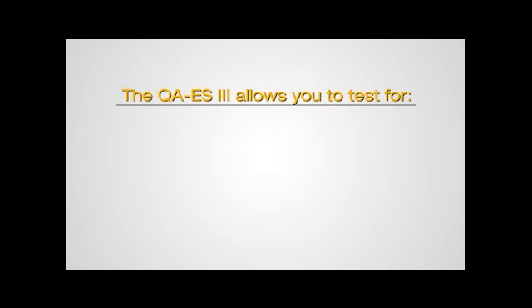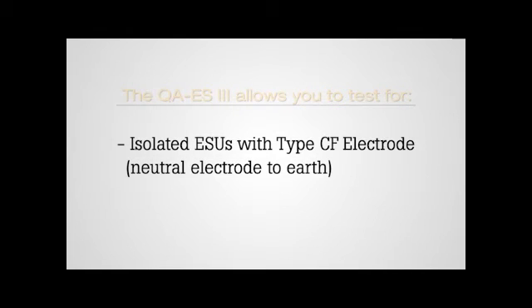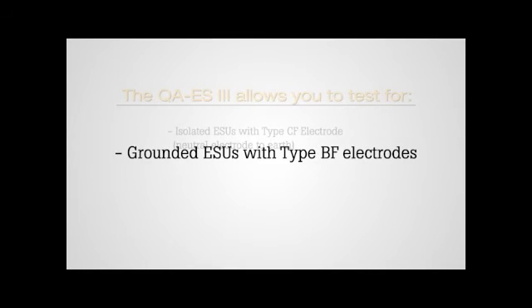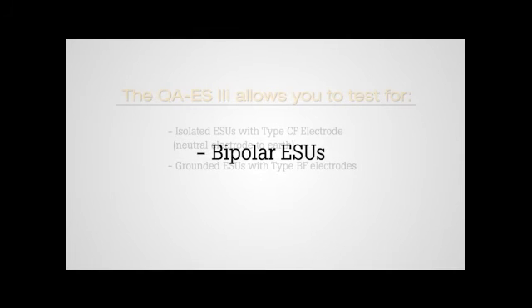The QAES-3 also allows you to test HF leakage for isolated ESUs with type CF electrode, neutral electrode to earth, grounded ESUs with type BF electrodes, bipolar ESUs, and vessel sealing.